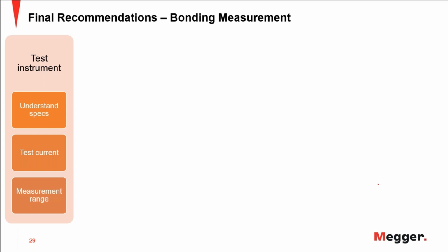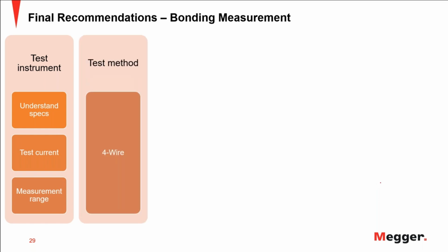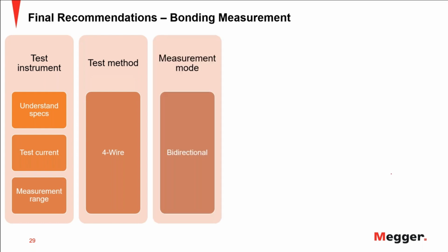So just to summarize the bonding section, you want to have the proper test instrument. You want to understand the specs, what voltage, what current it is using, in the measurement range, how low can it go in the measurement. You want to pick your test method. Really, for bonding measurement it would be the 4-wire. Definitely continuity verification won't be the best way. 4-wire will give you the correct result. Measurement mode, well, it depends. Typically you can use the unidirectional, but bidirectional will definitely give you the accurate result, especially because you have such a long distance to measure, you could have different temperatures in between those sections, and that is going to affect your result.